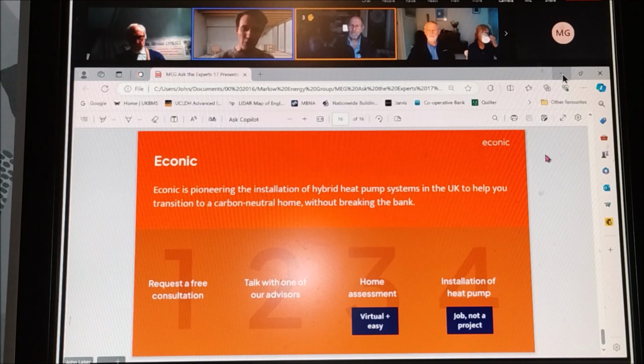The core question for us to always ask is: which rooms are cold in your house? Because typically the homeowner already knows their house the best, and many times thermal comfort is very subjective. So just ask the family which rooms are typically colder or warmer. And while you've got the plumbers on site, you might as well fix that problem. That's typically the best indicator of which radiators need to be upgraded.